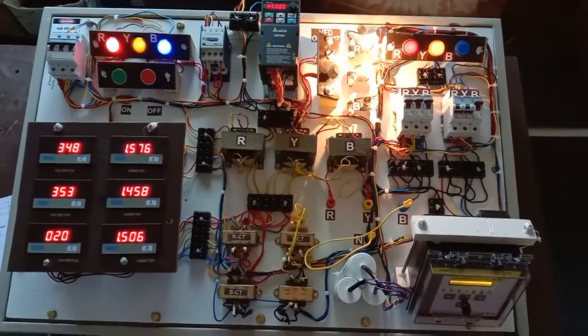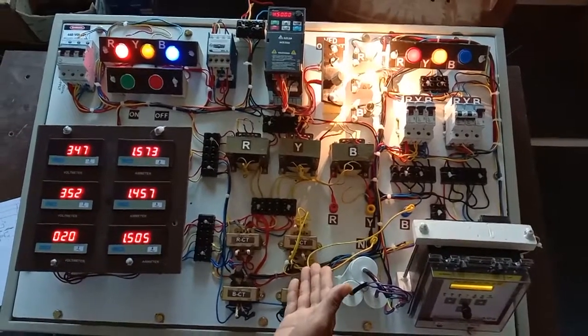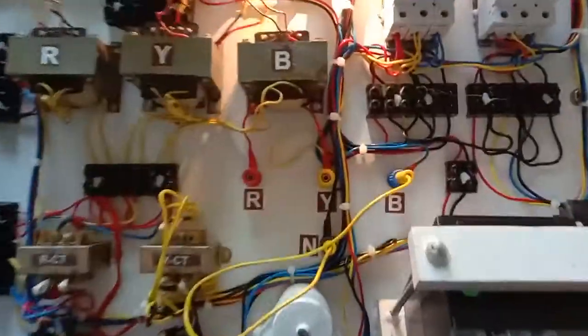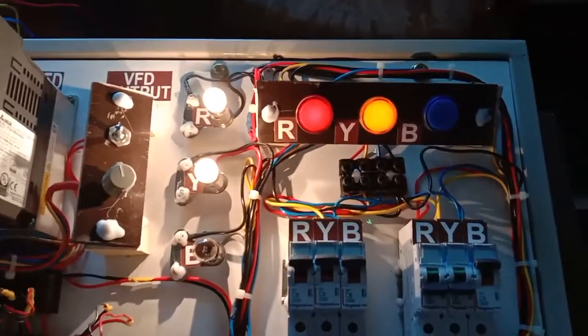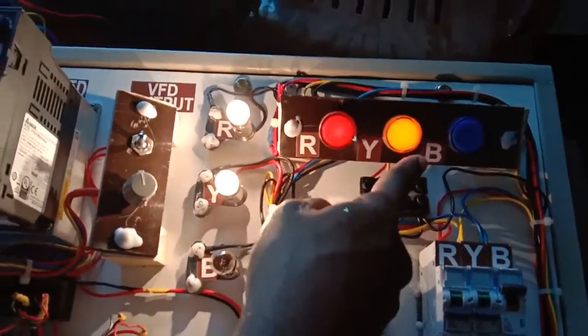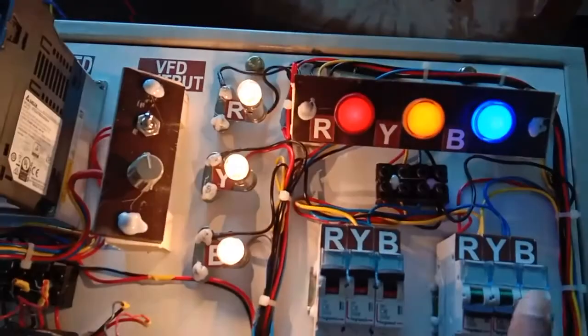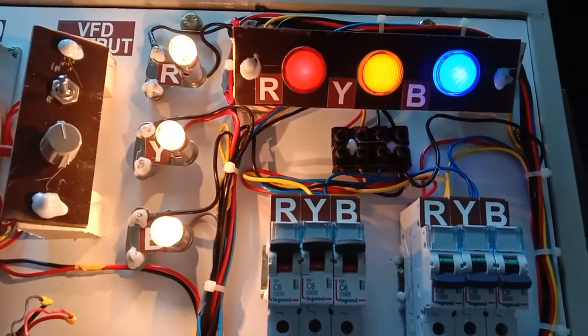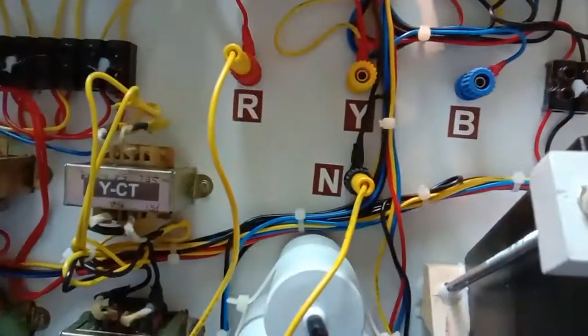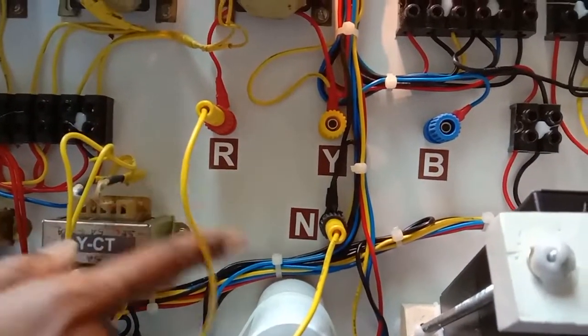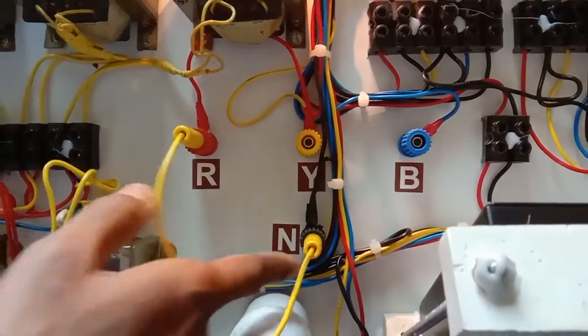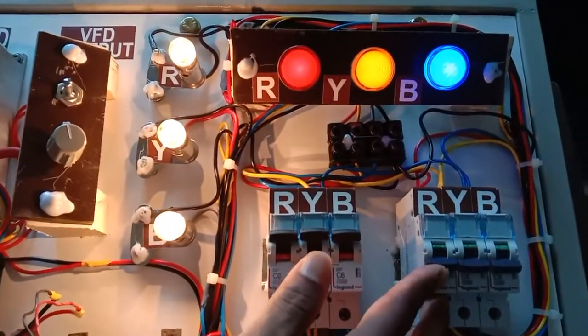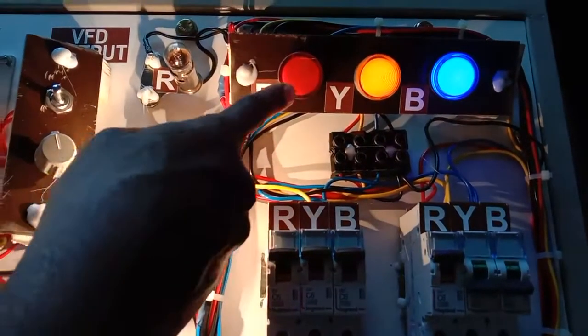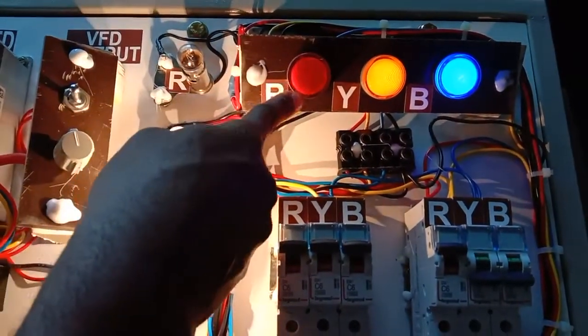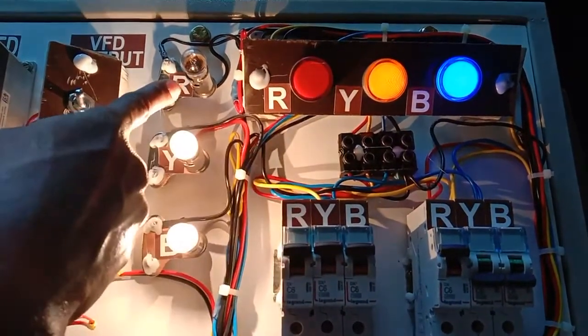So you can create the respective LG fault on R phase, Y phase, B phase. You can see these LED indications. Now the fault is in B phase, and if you want to simulate the fault in R phase to neutral, connect the patch cord from here to here and switch on this R phase fault creation MCB. So these are the indications. R phase LED is off and the load is also off.